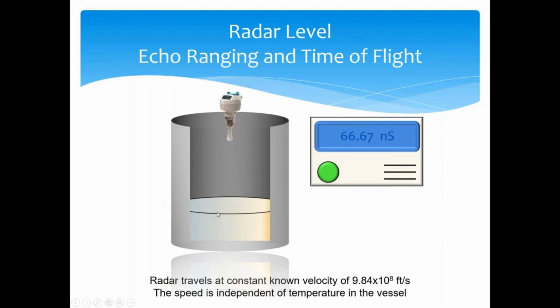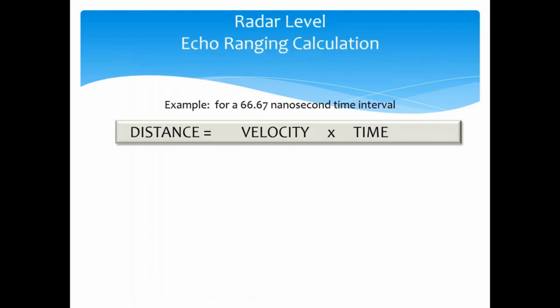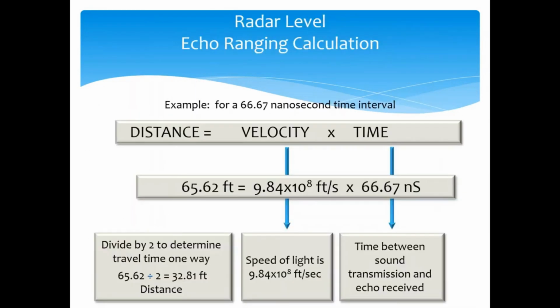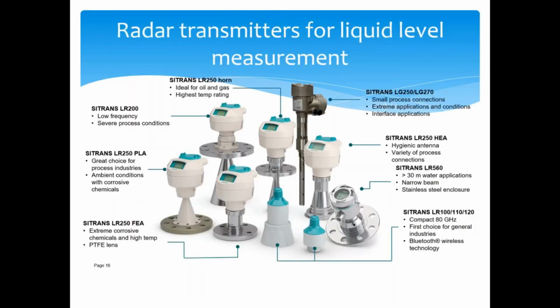And instead of looking for a change in density, we're looking for a change in dielectric. So any change in dielectric will reflect that signal up. Again, we measure the amount of time that it takes and divide that by 2. It tells us the distance, how far away we are from the liquid. Then we calculate your level based upon that. So two key takeaways: ultrasonic is the speed of sound through air, and it's looking for a change in density. Radar is the speed of light through any media, and you're looking for a change in dielectric. We'll talk more about how that relates to the way these technologies work in the coming slides. And again, I simply put a quick slide here that shows the different radar transmitters that we offer. So your traditional horned, Bluetooth style, solids radars, and guided wave.